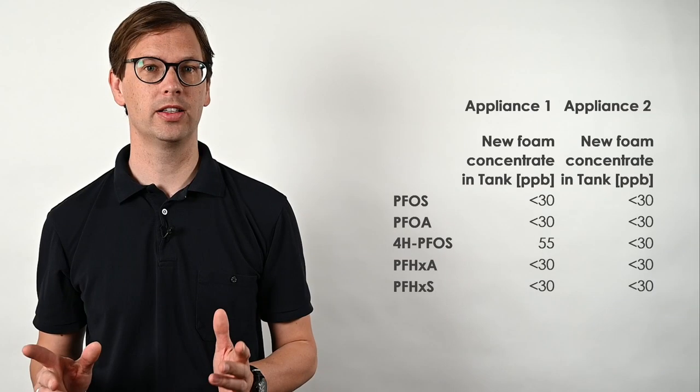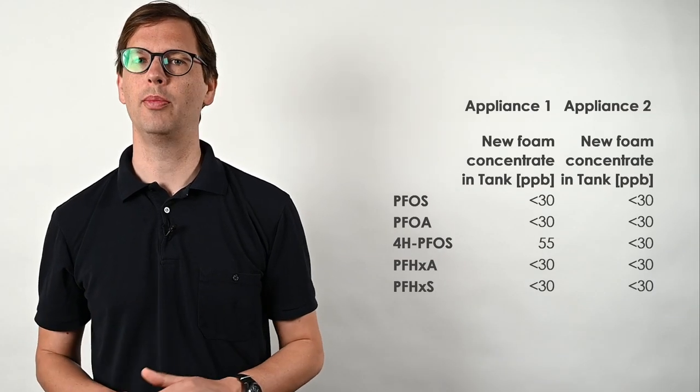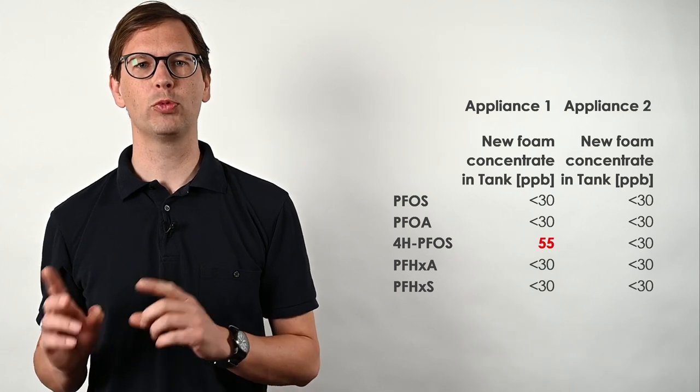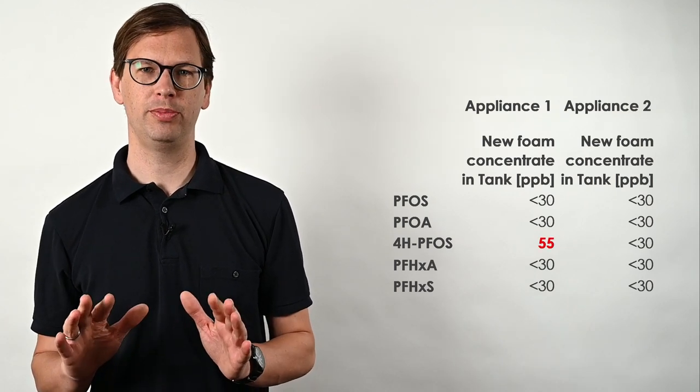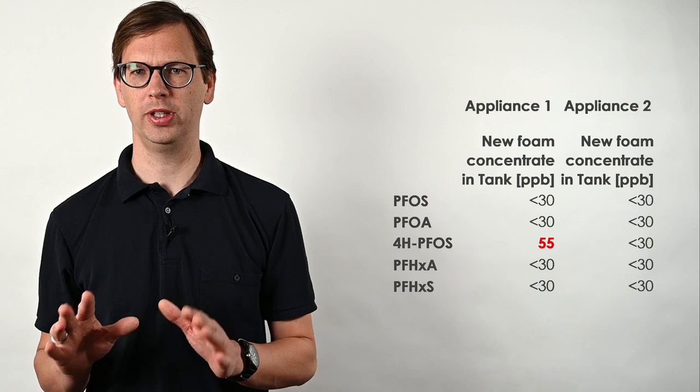Is this cleaning sustainable, or do some hidden residues from the old foam concentrate find their way into the new fluorine-free foam and contaminate that with PFAS? To find out, you can do another PFAS analysis of the new foam in the tanks a couple of years after the cleaning. And here is an example. All values are below the detection level, except one. It shows about 55 ppb of so-called 4H PFOS.